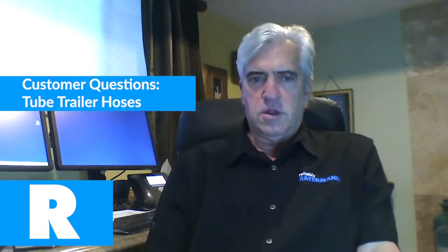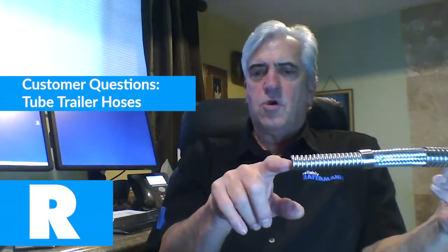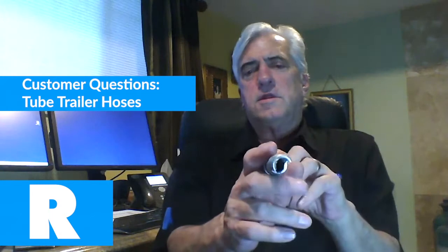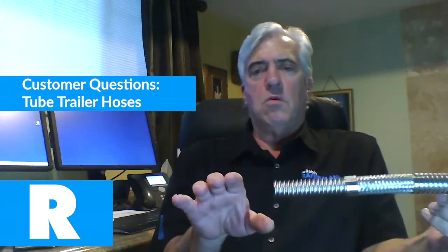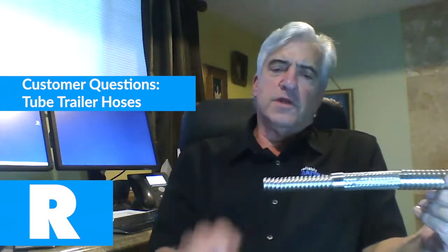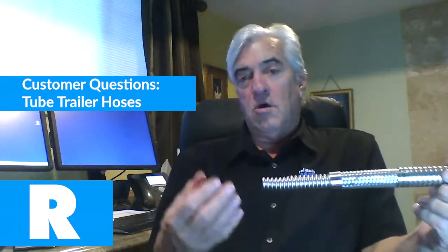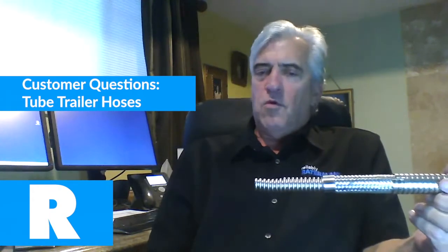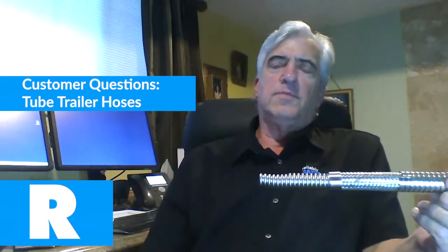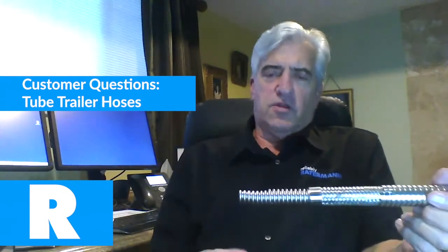Cryogenic hoses are different than your standard pigtails used in a fill plant. Cryogenic hoses use a corrugated inner core, and this is corrugated stainless steel. When you have this as your inner core, you have zero permeation. This is a great hose for transferring liquid and gas at lower pressure levels. These hoses are typically anywhere from 400 to 1500 psi maximum working pressure on your standard liquid transfer hose.